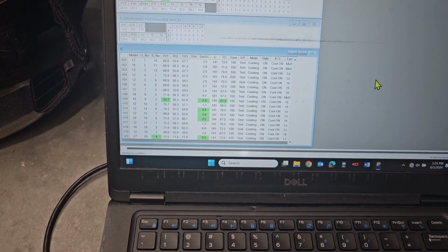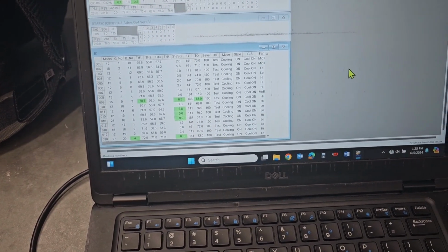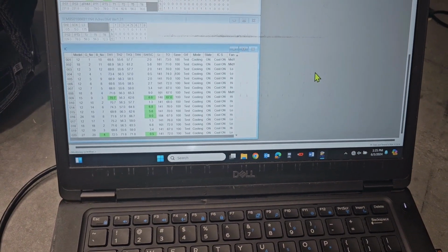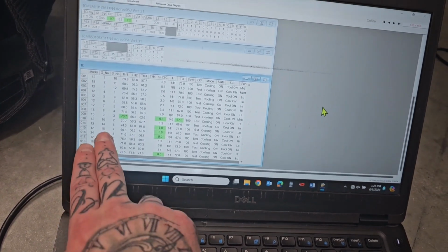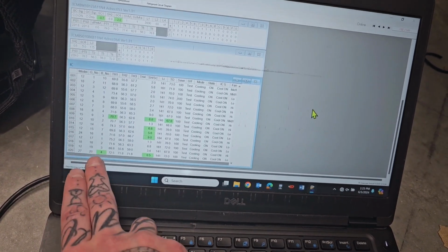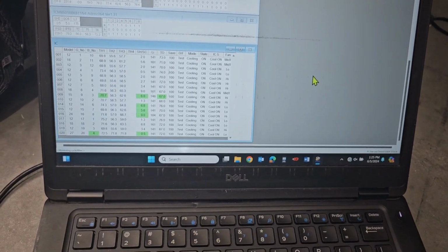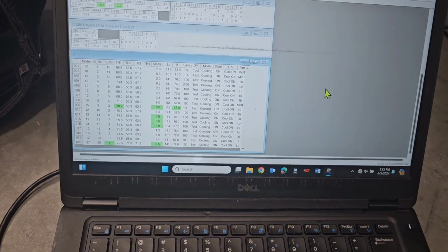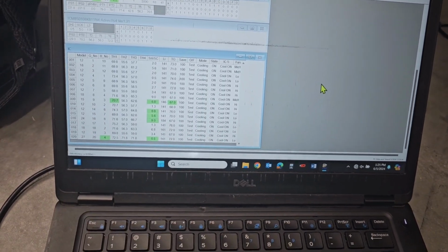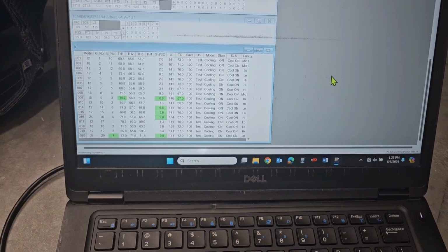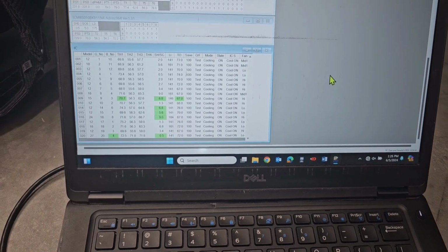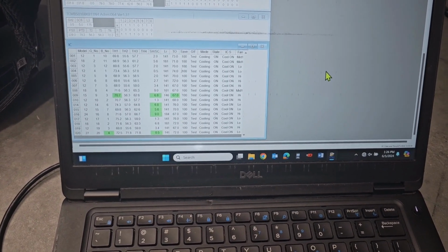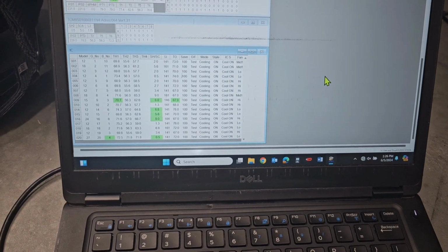So you always have to think to yourself, okay, I think this is the problem, how can I prove it? So I think that 6, 7, and 8 and port 4, their indoor units have bypassing LEVs. So I went through, closed those 3, closed that last one, and everything started to work fine. Again, you have to make sure that you're not just simulating that the system now has more refrigerant, so it's able to give more refrigerant to the other units.